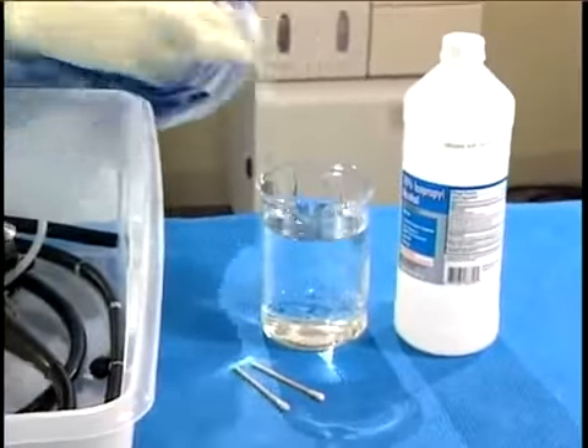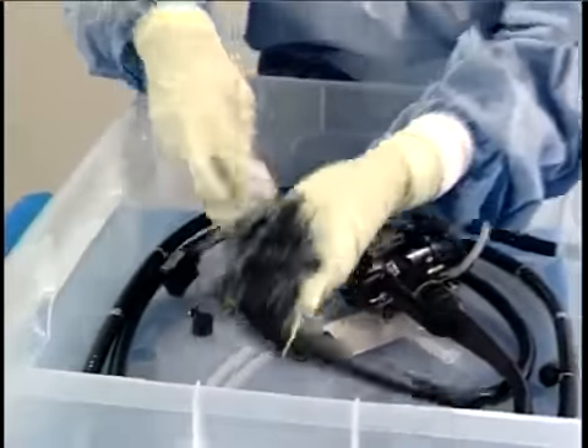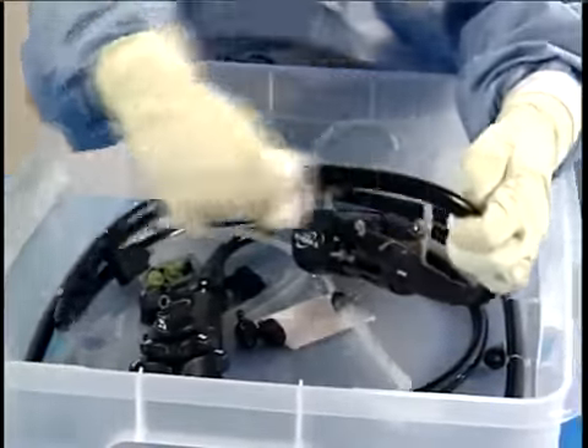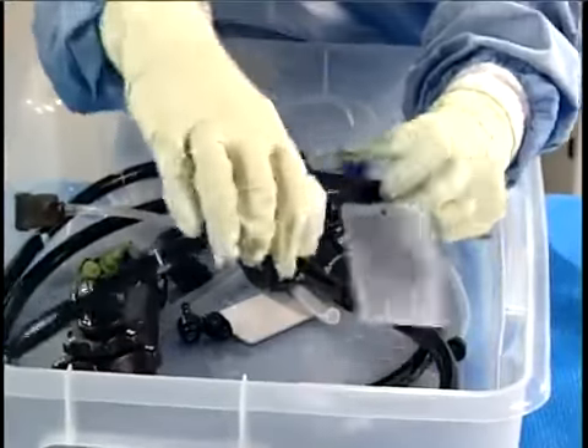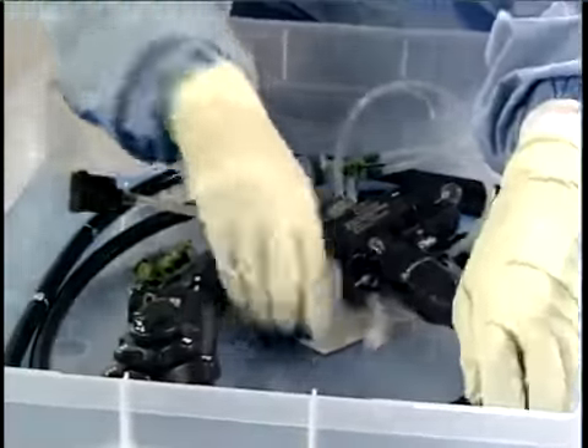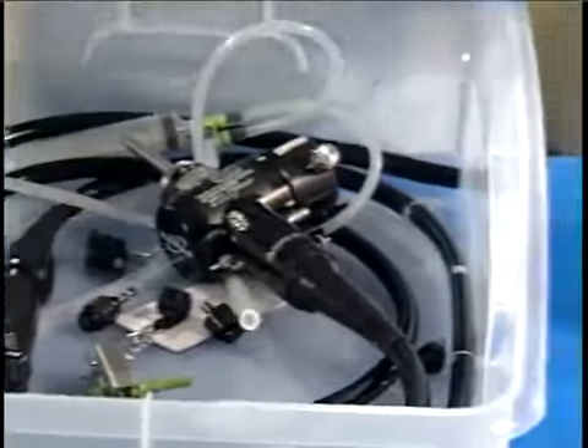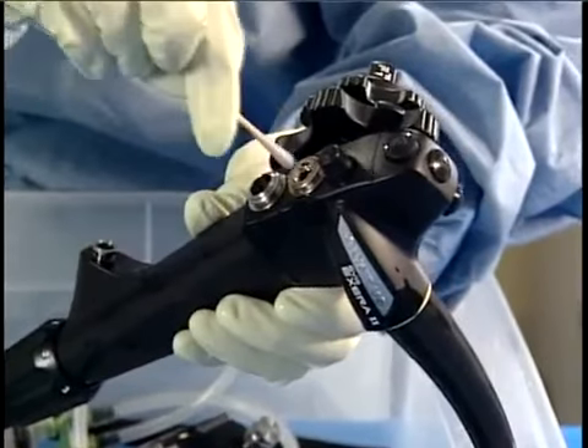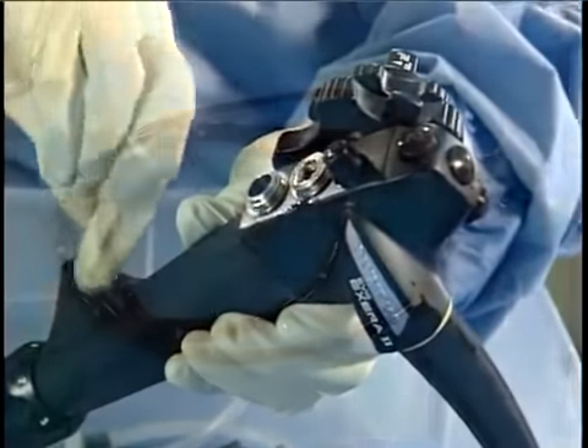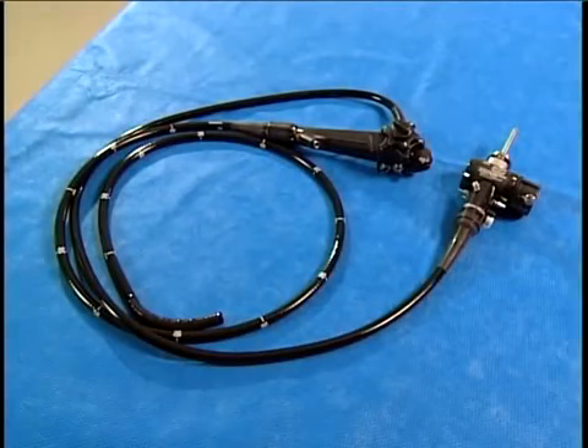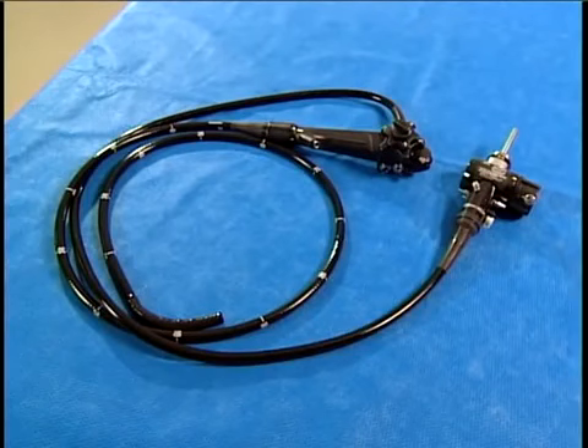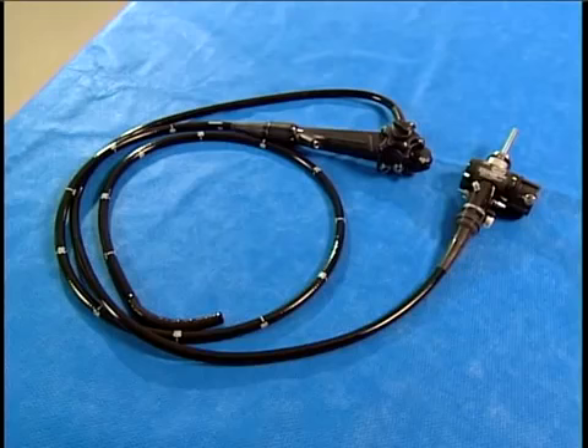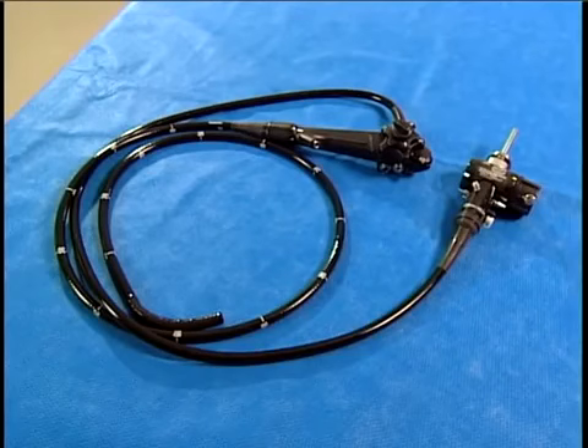Use a sterile lint-free cloth moistened with 70% alcohol to remove any remaining water drops on the external surfaces of the endoscope, the channel plug, and the injection tube. Use sterile cotton swabs to dry inside the valve housings and instrument port. Your endoscope is now reprocessed and ready for use in examining another patient, or for storage and use at a later time.